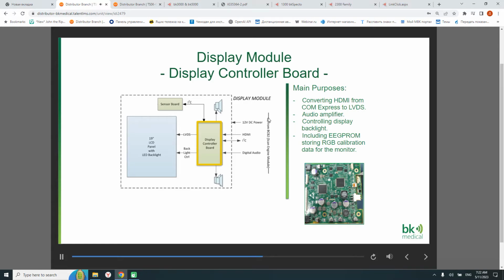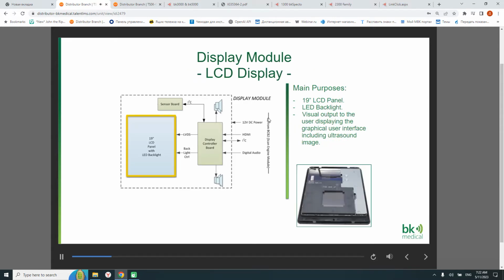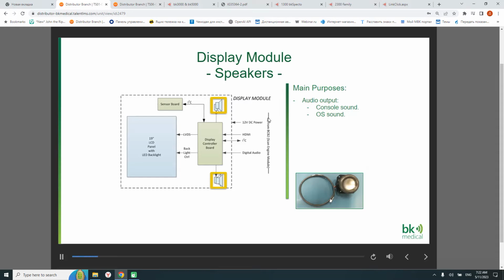The hardware monitor function on the SCP card controls the backlight and accesses the EEPROM via the DDC interface in the HDMI cable, which is an I2C connection. This interface is not used by the graphic system because this display has fixed settings. The 19-inch LCD panel is displaying the graphical user interface, including the ultrasound image, to the user. The 19-inch LCD panel integrates a backlight lamp, which is a white LED. The speakers are reproducing the sound coming from the display controller board. There are 2 speaker units working in stereo.